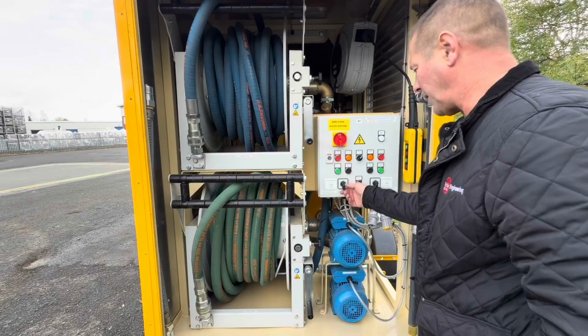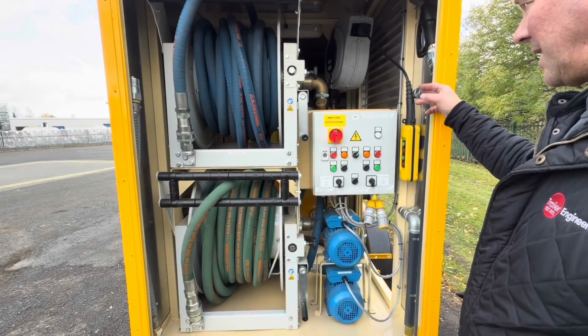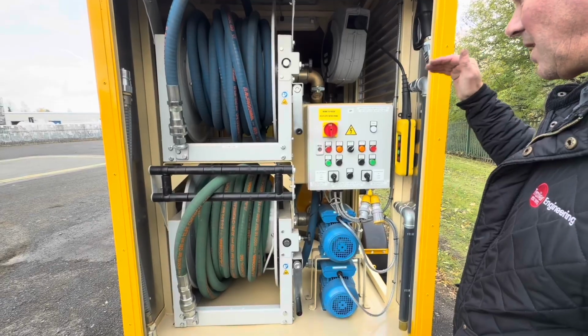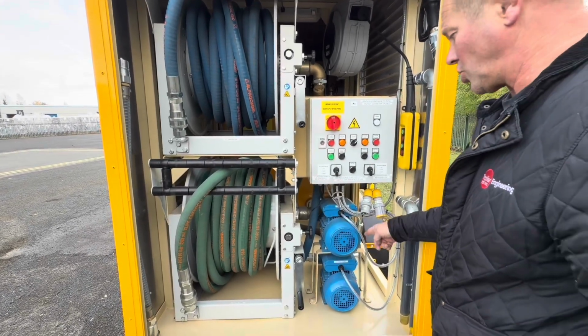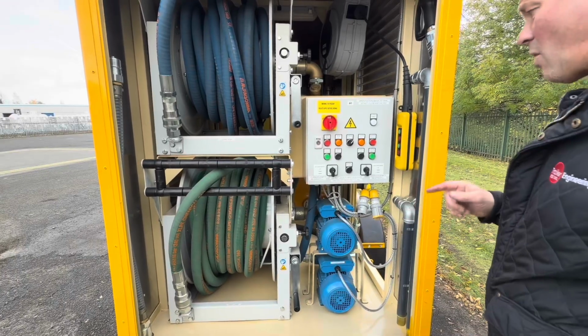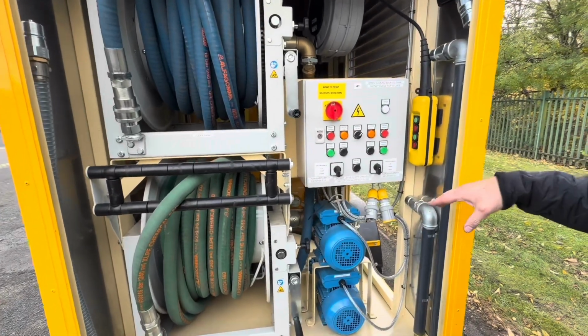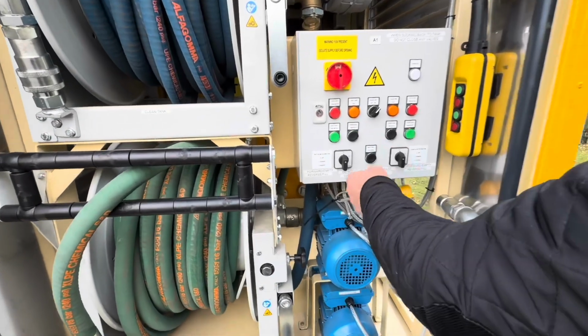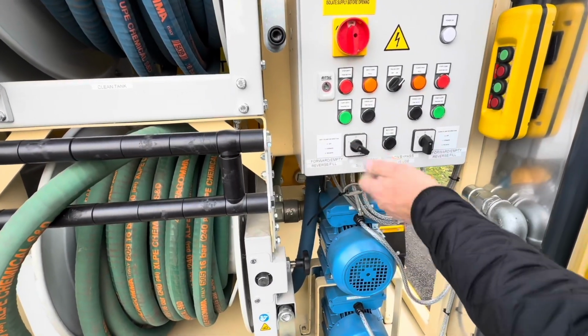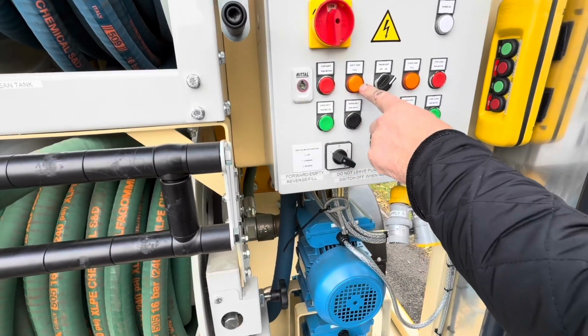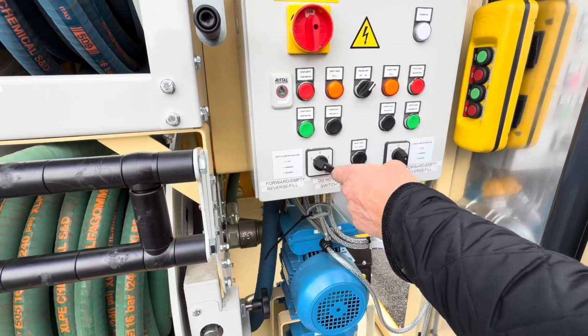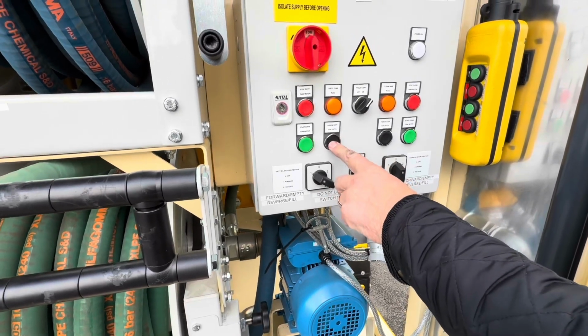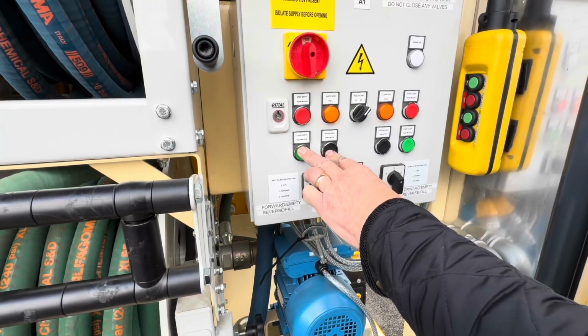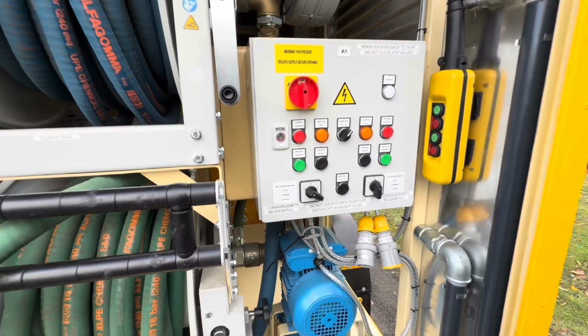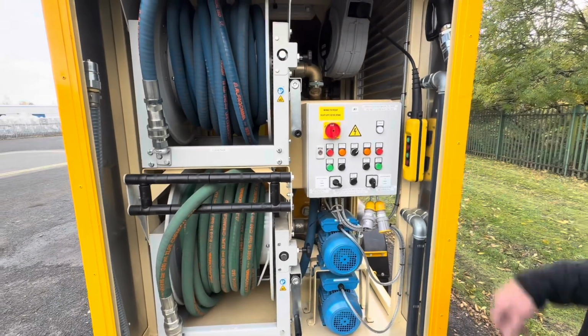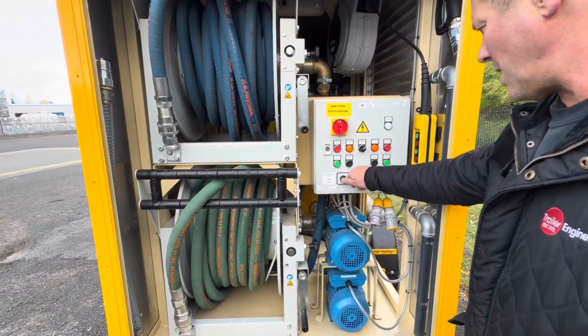If at some point you're filling the tank, there's an overflow sensor in the tanks as well. So as the tanks fill, if they're going to overfill, they send a message to here, cut your pump off so you can't overfill the tank. And then the way you override that, because obviously the pump's being told to switch off, to be able to empty the tank, switch it back to empty. So it'd be forward for empty. So in this case, your tank's full, that light will come on. Switch it to empty, and then you can override it by holding the override switch and then switching the pump on via that, and that will empty some out of the tank. So then the pump will go back to the state where it's not being overfilled. So just an override facility there.